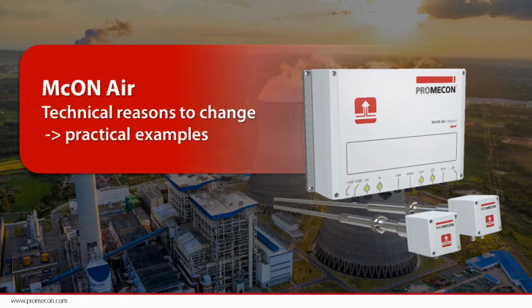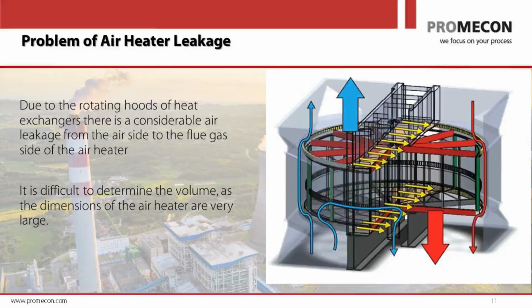Let's have a look. The reason is because the airflow is a process gas. What do I mean by process gas? A process gas is typically a hot gas that contains dust when it comes to thermal processes. And it's not very easy to measure process gases, and it's very hard to measure them reliably and drift-free over longer periods of time. So when it comes to air that goes into the boiler to transport coal to the burners or to oxidize the coal in the burner, when it comes to primary and secondary airflow, why is it so hard to measure these airflows?